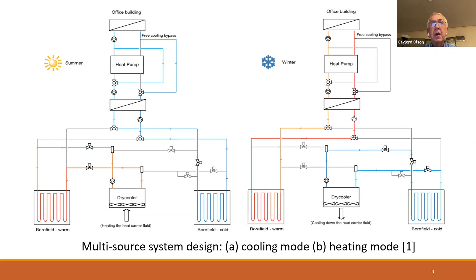But what's going on in the left-hand half of this screen is the hottest summer afternoon. So you've got nice cold water from the right-hand bore field, and you're preconditioning the left-hand bore field with the dry cooler — we should really call it an air-to-liquid heat exchanger, since it's not only a cooler, it's a cooler and a heater, whatever you want. Now, they're showing bypassing around the heat pump, so they're getting water that's cold enough to not even bother with the compressor and the heat pump. So they've got the economizer mode operating there, which is kind of nice.